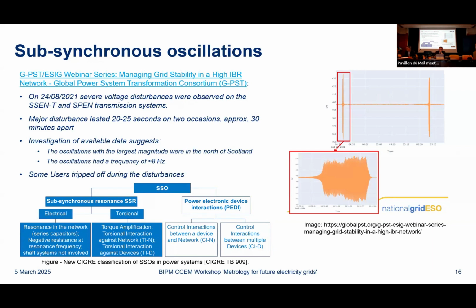So you can see it was on the 400 kilovolt network. And the amplitude variation in the voltage for a short period of time was around plus or minus 30, 40, 50 kilovolts even. At the time when it happened, it was quite surprising and quite concerning, and it did cause some assets in the grid to activate their protection systems and disconnect. And so since then, everybody's been on high alert to try to understand those types of oscillations, where they might potentially come from.